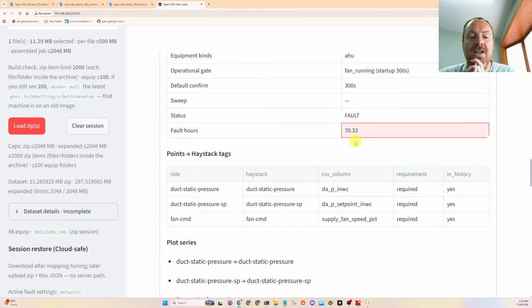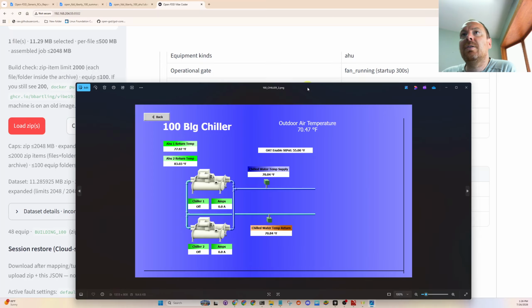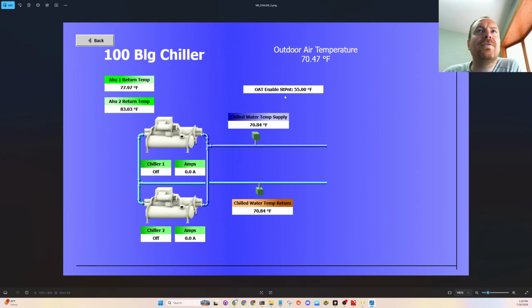I think the fix that I've seen for this is we start the chiller purely based off of cooling valve position. So let me just get back to this. I feel like I can best explain this. Okay, so for the chiller, I'll have to do a little deeper dive to see if it comes on purely on outside air temp or not. But there should be some kind of interlock where the chiller is scheduled, or it comes on based on demand, based on cooling valve position of the air handling units.